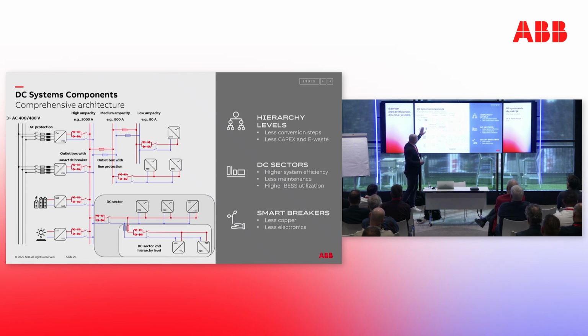We can have isolated or non-isolated connection, depending on the system itself. In this case, the connection should be isolated because of the type of smart breaker, as it's called in the description used. We always have a solid-state-based circuit breaker protecting the in-feed, as well as the DC sectors.